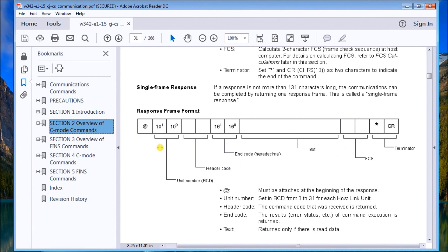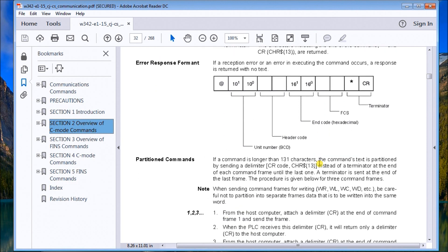The response from that message contains the at sign again, the unit number that's responding, and the header code — which is the same code we sent out. Then we get an end code, which indicates whether or not the information was received correctly. After that comes the text: if we're reading information, this is the data read from the controller. Then we get our checksum returned from the controller so we can verify the message, and finally the terminator — the asterisk and carriage return.